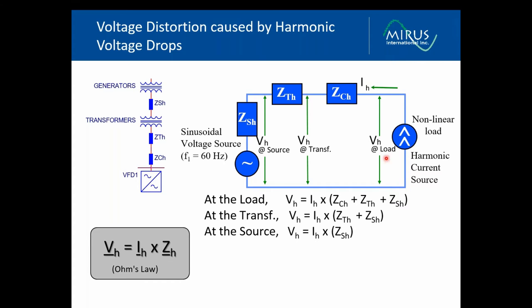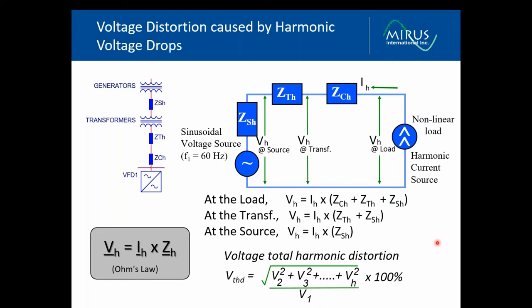And since the impedance that these harmonic currents will see is highest in that we have the cable impedance, the transformer impedance, and the source impedance, you will get the largest voltage drop at the loads. And the cumulative effect of all the voltage drops is what creates our voltage distortion. As you move upstream in the system, the voltage drops will be less at each harmonic, the voltage distortion will be less. The least amount of voltage distortion will be measured at the source or the generators in the marine applications.